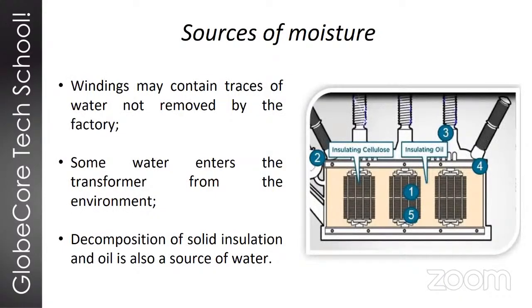So before we go into detail, let's quickly recap the three main sources of water in the transformer. So first of all, it's the residual water, you may call it, in the solid insulation that has not been removed during the production process at the factory. And manufacturers sometimes, or in many cases, do not possess the necessary infrastructure or equipment to ensure the required level of humidity or the required dryness of new transformers. And another common misconception is the assumption that new oil is dry. So new oil is not necessarily dry. It could have accumulated moisture already. And so transformer companies might actually inadvertently introduce significant amounts of moisture into their new equipment.